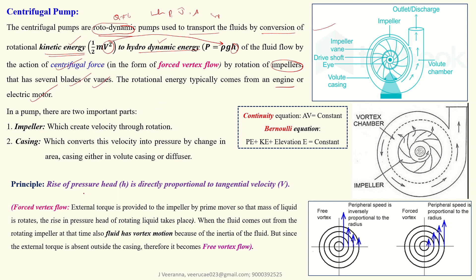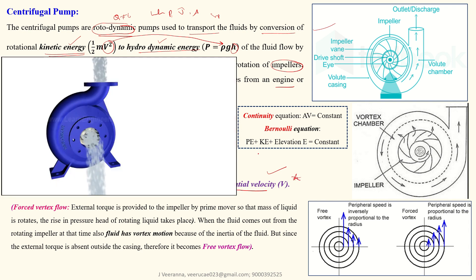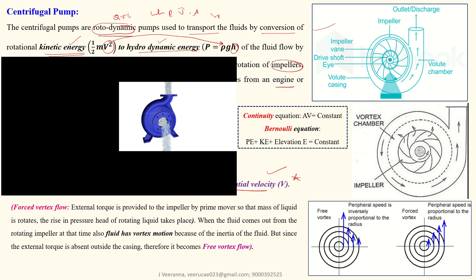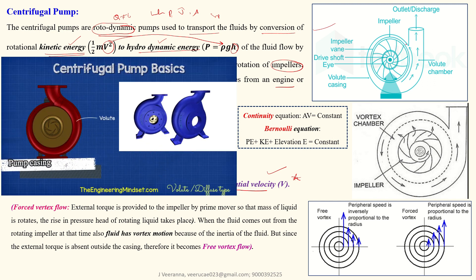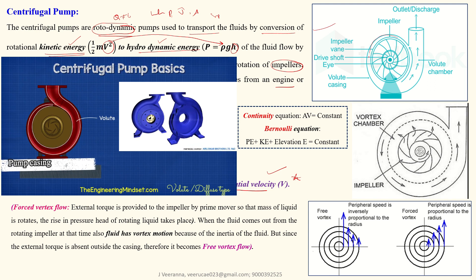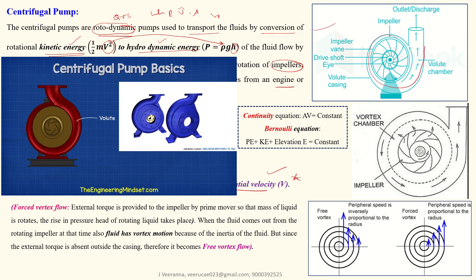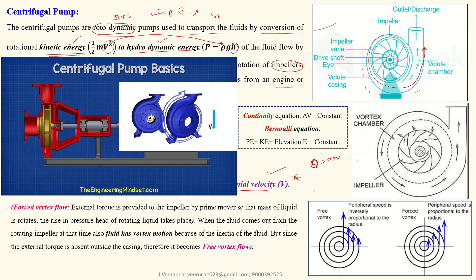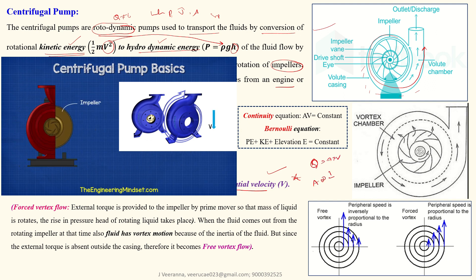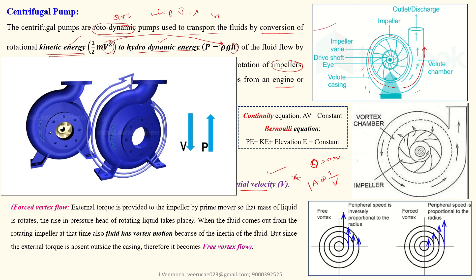To summarize: the rise in pressure is directly proportional to tangential velocity. Looking at the diagram, the casing area gradually increases toward the outlet with no other outlet sections. From the continuity equation, Q = A × V, so area is inversely proportional to velocity — when area increases, velocity reduces.